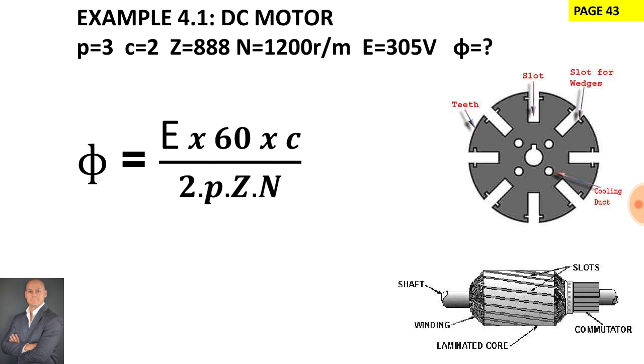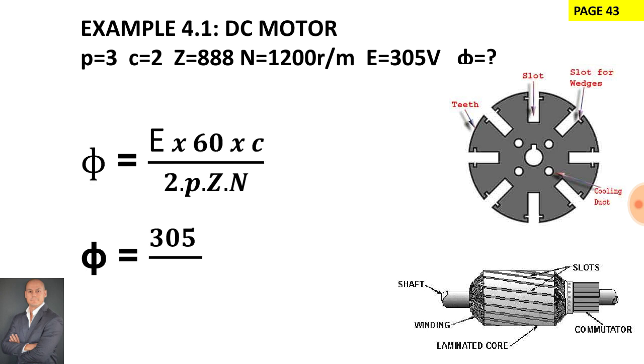Let's substitute all the values in. Our generated EMF is 305 volts and that is our constant 60 multiplied by the number of parallel paths and this is a wave-wound machine therefore the number of parallel paths is 2. There's our constant of 2 multiplied by the pole pairs. This is a six pole machine therefore there are three pairs and the total number of armature conductors is 888.